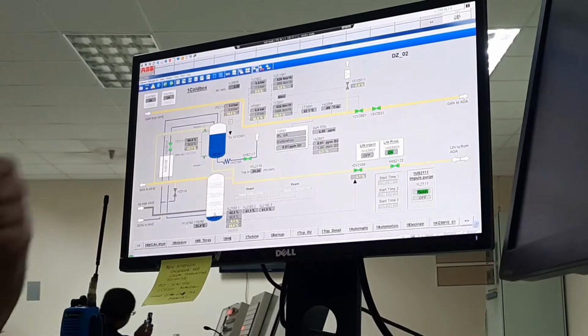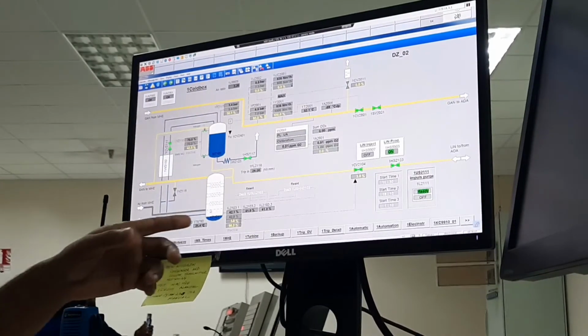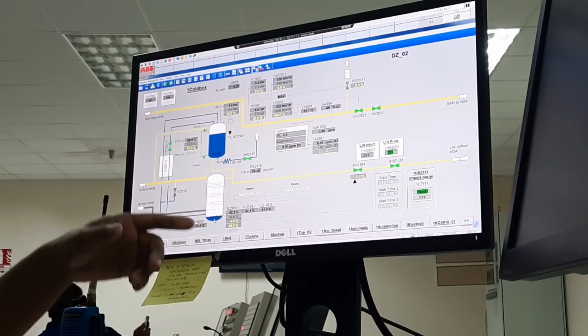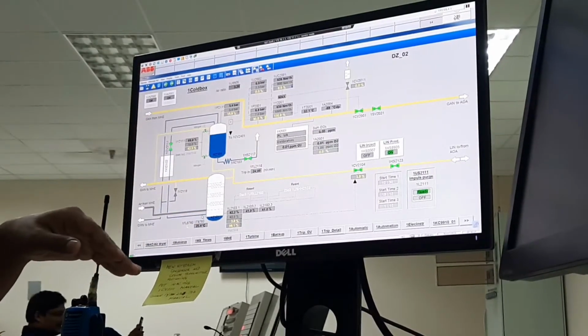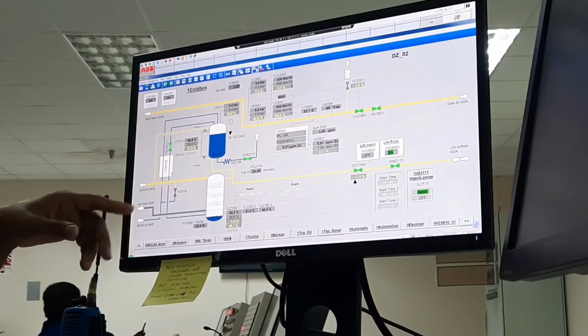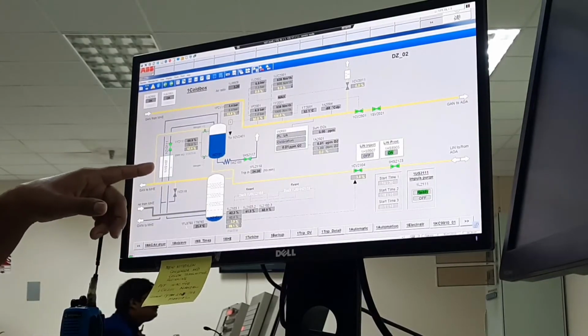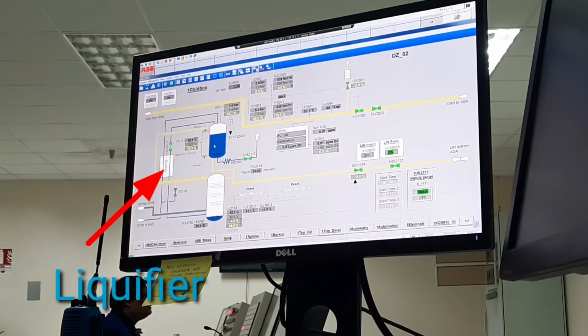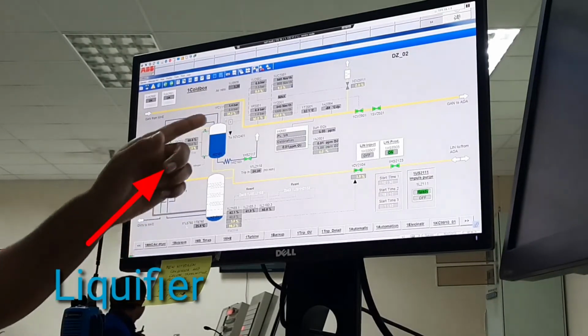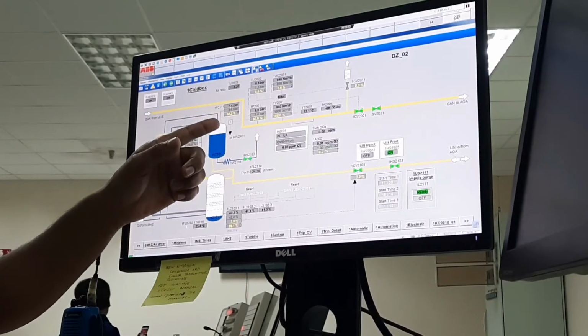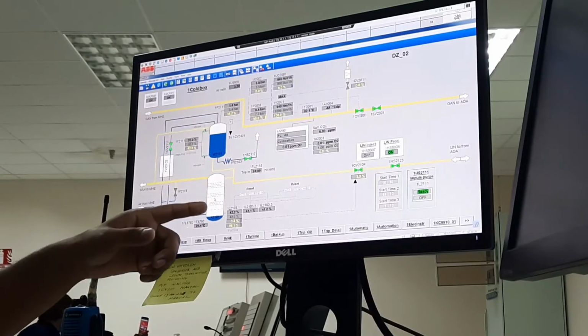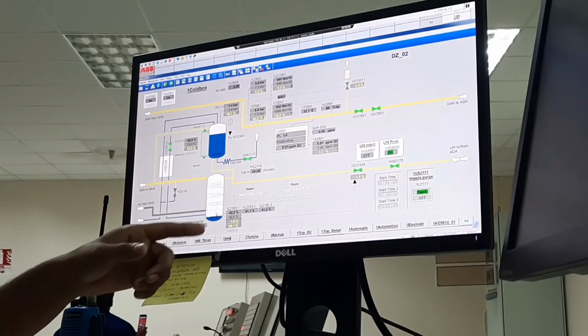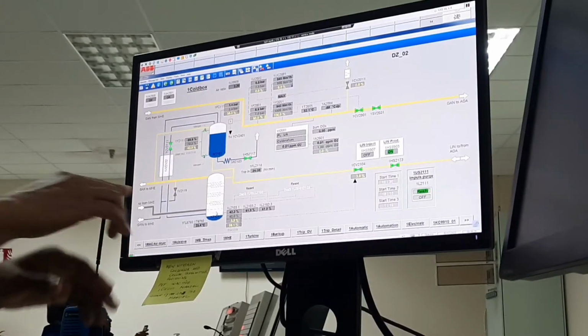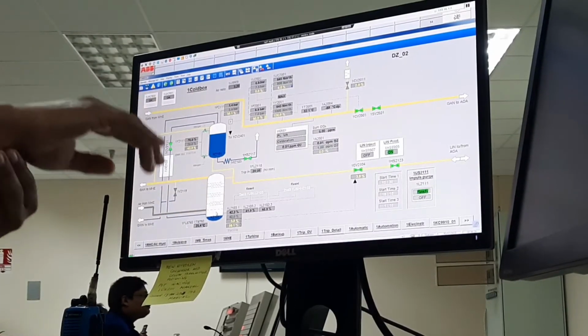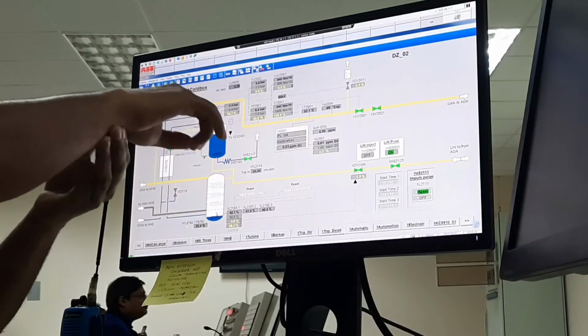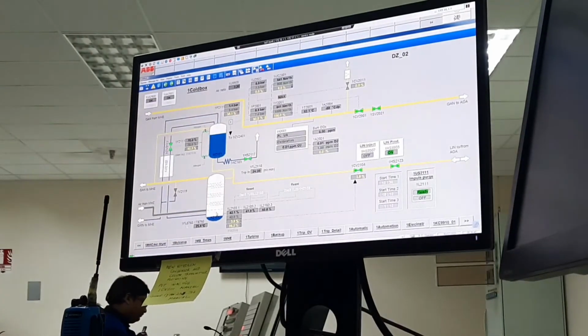But if it goes more than 42, what will happen? When more than 42 nitrogen has accumulated, this nitrogen will go by this line. You see, by the liquefier, it will go to the condenser. How much pressure? We are giving this 3.4 kg pressure, and 7 kg here. When it is coming down, this pressure reduces. When the level increases, pressure also increases. When pressure increases, this product will go to the 3.4 kg pressure condenser.